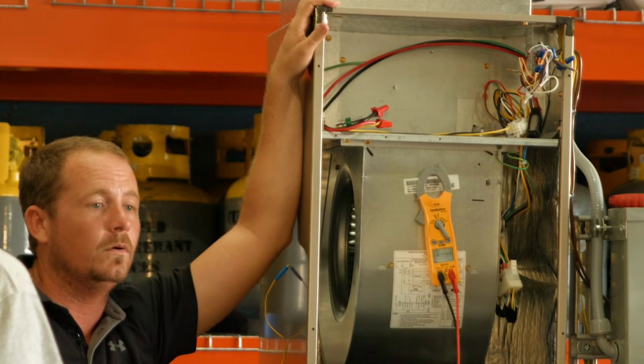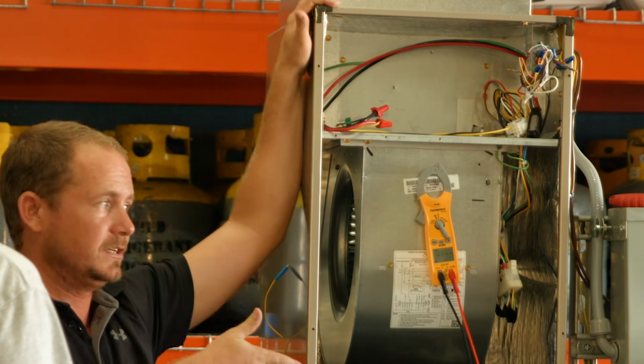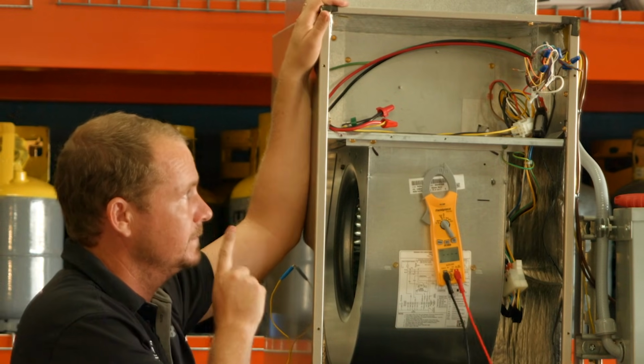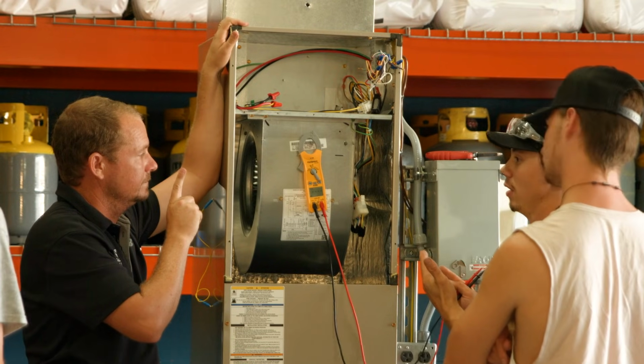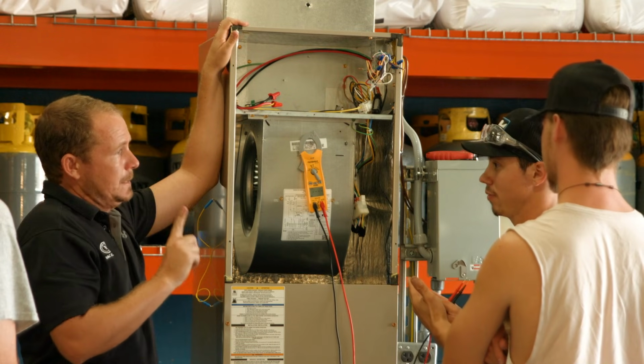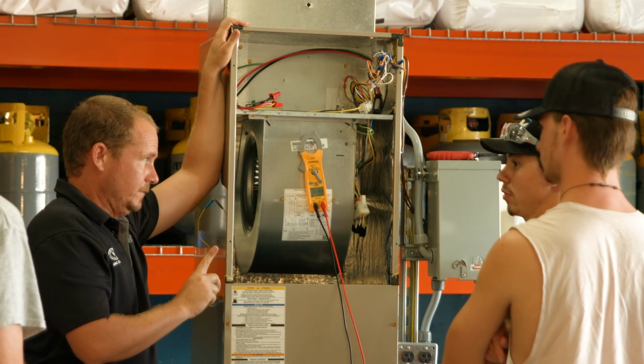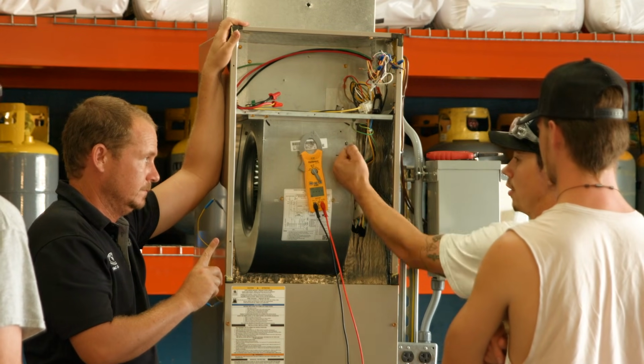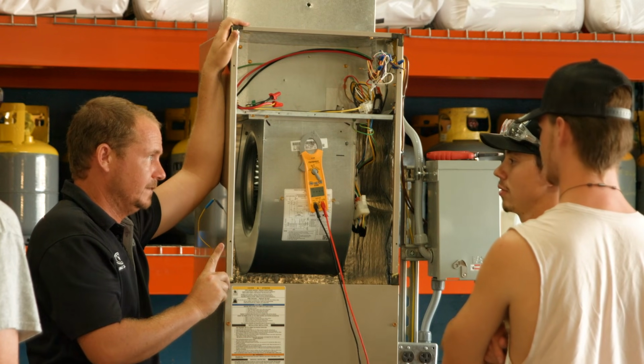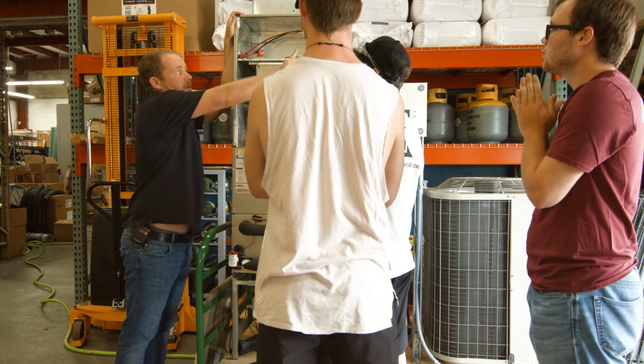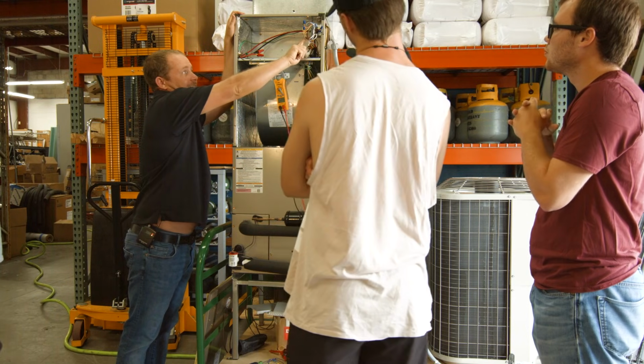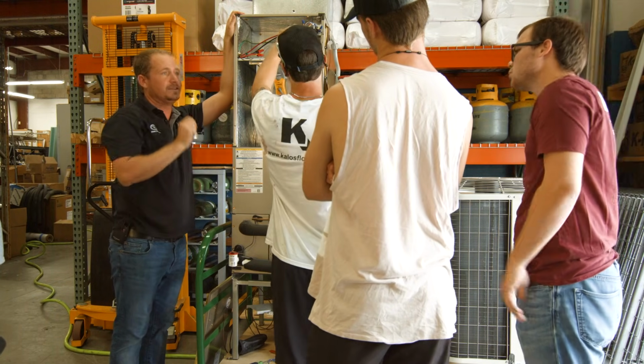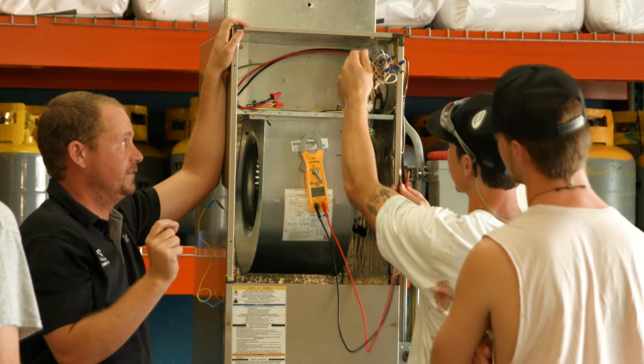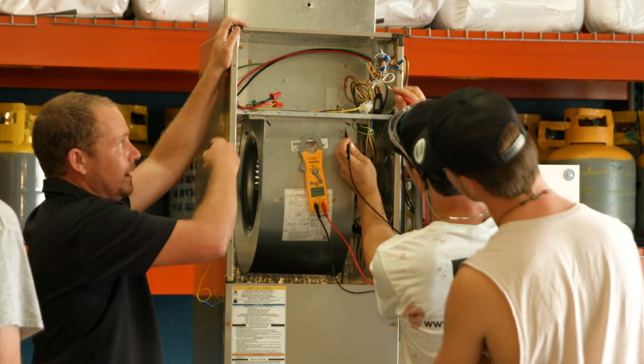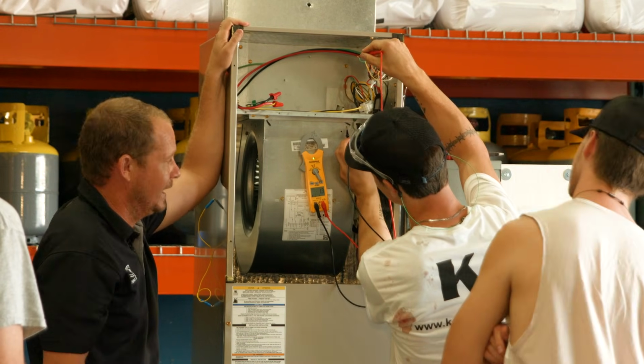All right, so what does that tell us? What's the conclusion? That there's a short because it's taking a shortcut off of the loads that it's designed to go through. Okay, so it's a short in what conductor though? In the blower. What conductor is that? Green. Green, got it. So, or G.